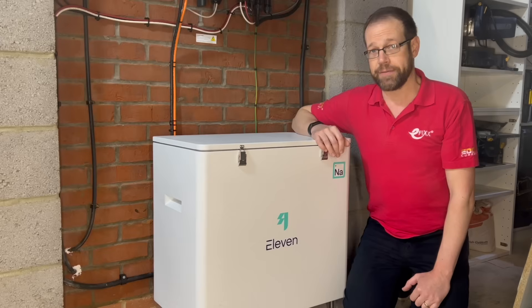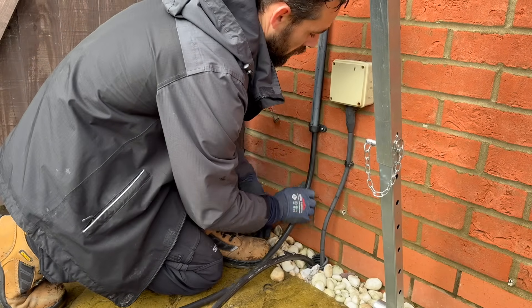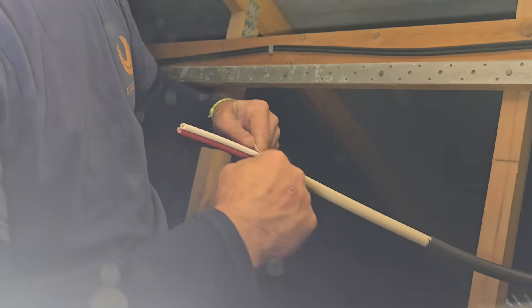This reinforced the decision not to have DC isolators on the new installation. Unprotected strings outside and in ducting aren't great, so the plan was to replace them with this beautiful bit of PV Ultra from Doncaster Cables. It's unarmoured as it's in ducting, and the tough sheath provides all the mechanical protection we need in this environment. That way, we don't need to get into a debate about earthing the metal framework on the panels.